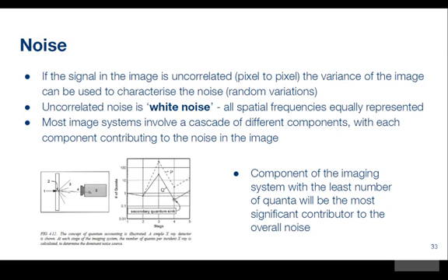So rather than having a camera-based system here, we might have an array of photo detectors that convert the optical photons into a digital signal. We can put that right up on the face of the screen, and that would reduce the quantum sink that we've got at that stage of the detector. So when we're designing imaging systems, we have to think about this.